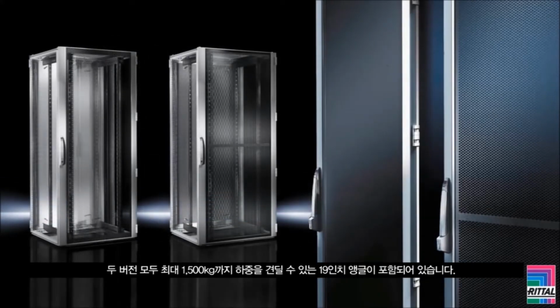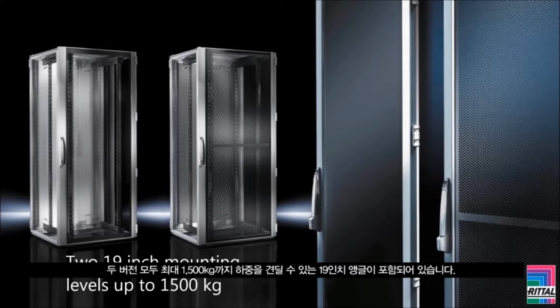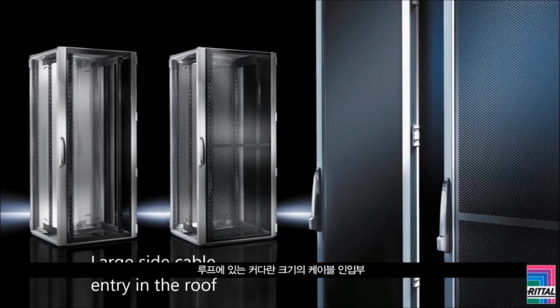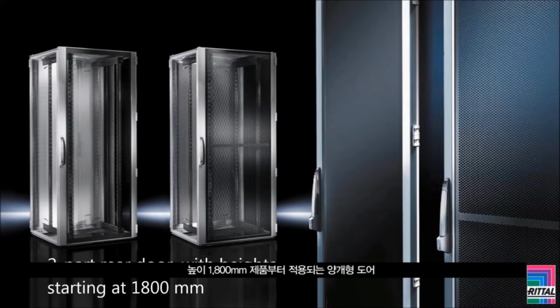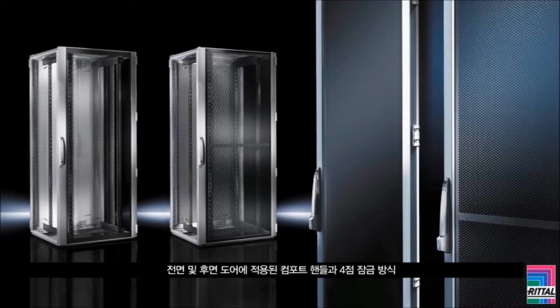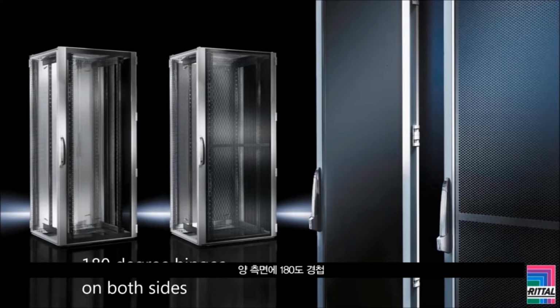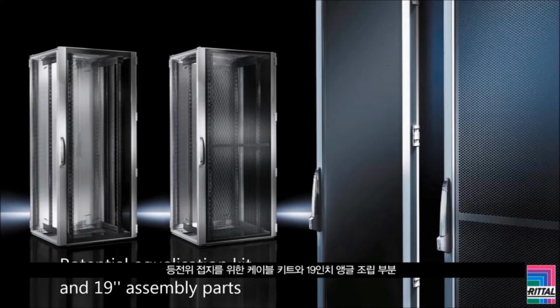Both variants include two 19-inch mounting levels up to 1500 kilograms, large, side cable entry in the roof, two-part rear door, with heights starting at 1800 mm, 4-point lock, with comfort handle, for customized locks at the front and the rear, 180-degree hinges on both sides, potential equalization kit and 19-inch assembly parts.